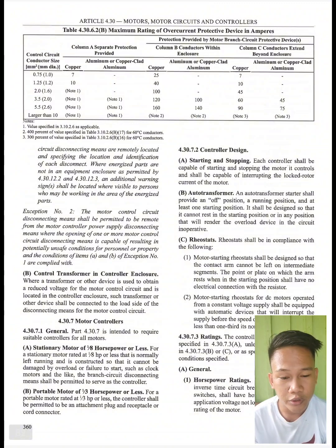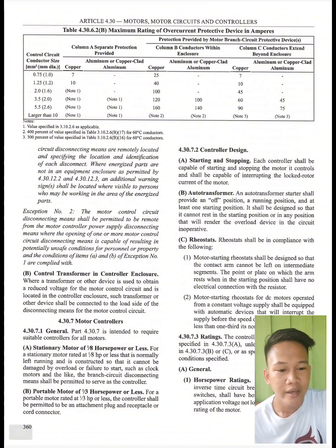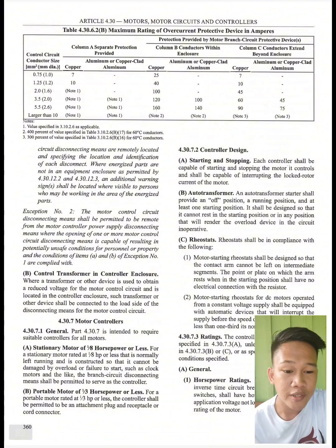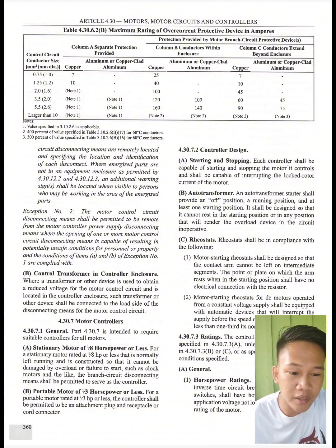B. Portable motor of 1/3 horsepower or less. For a portable motor rated at 1/3 horsepower or less, the controller shall be permitted to be an attachment plug and receptacle or cord connector. So next is 4.30.7.2, controller design. First we have starting and stopping. Each controller shall be capable of starting and stopping the motor it controls and shall be capable of interrupting the locked rotor current of the motor.